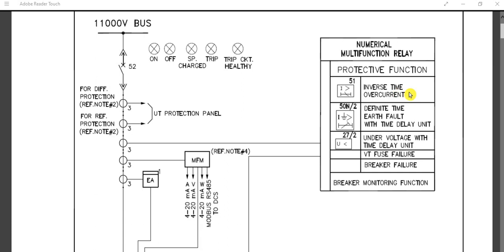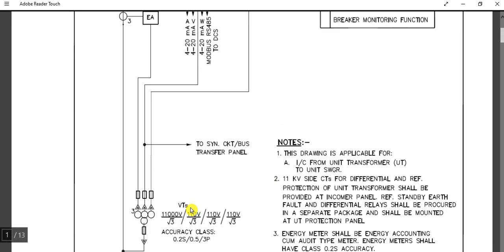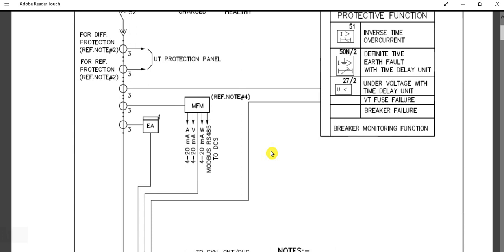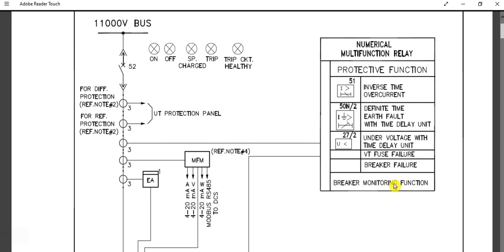The protection functions of the numerical multi-function relay are: 51 — inverse time phase overcurrent with IDMT characteristic; 50N/2 — definite time earth fault relay with time delay; 27/2 — undervoltage relay with time delay. Also monitored are VT fuse failure and VT healthiness on the secondary side. Breaker monitoring functions are also included in this numerical multi-function relay.